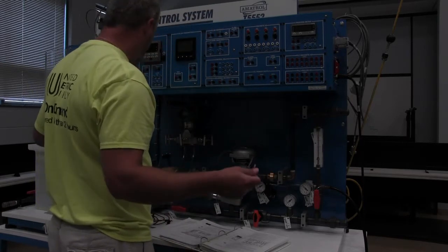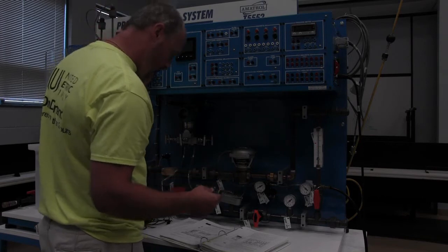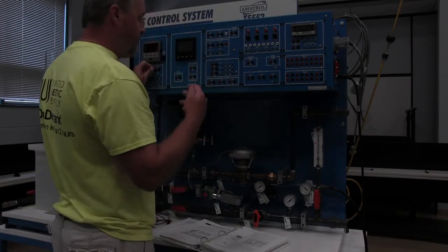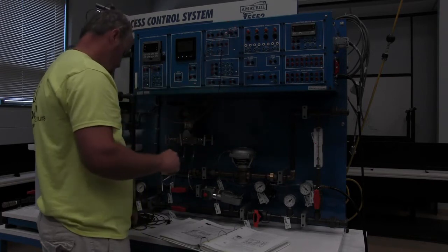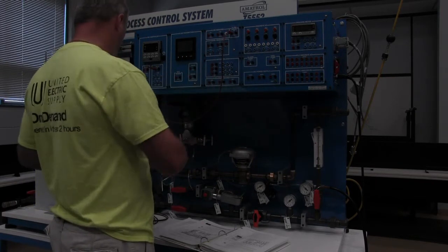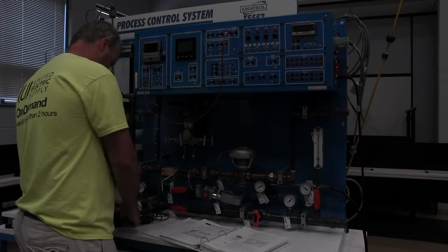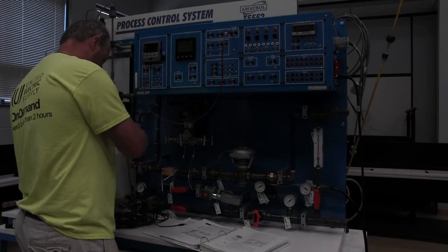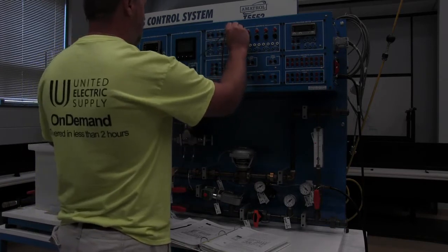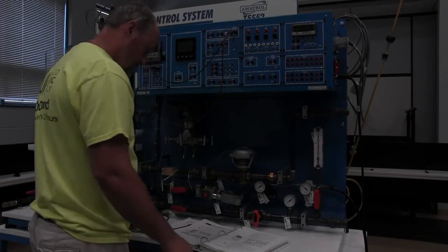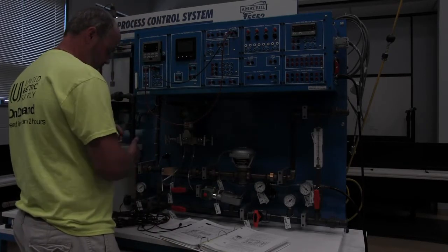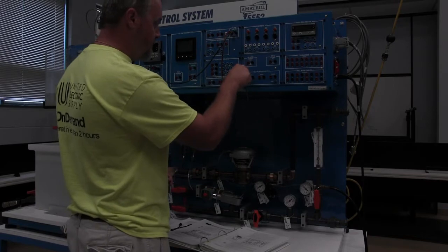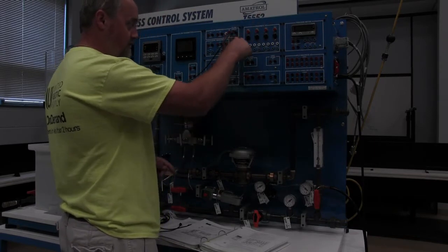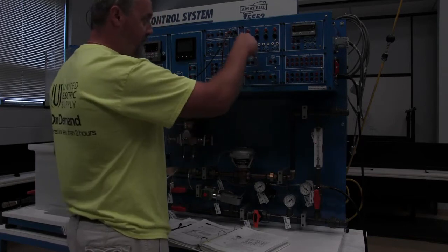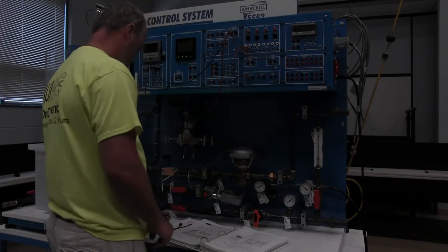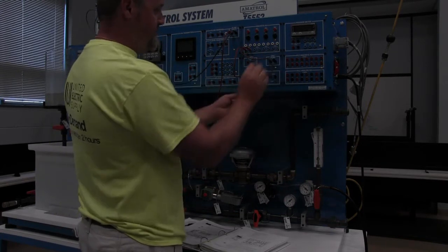So we're going to come off of the analog output, and we are going to go to the flow valve, positive to positive, and negative to negative, once I find one long enough. And then we're going to wire up the pump circuit. So we're going to come off of 24 volts. We're going to go to the selector switch. From the other side of the selector switch to the pump. From the pump's negative back to the negative of the power supply.